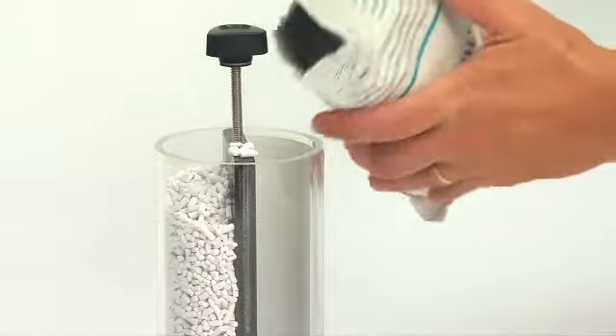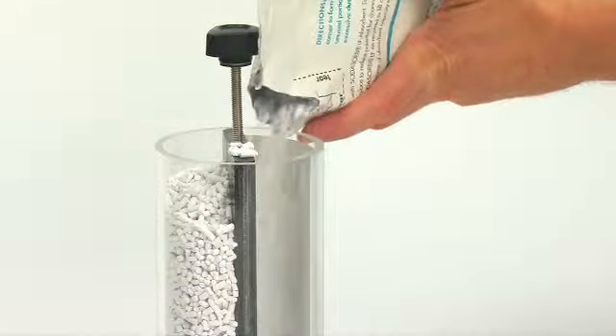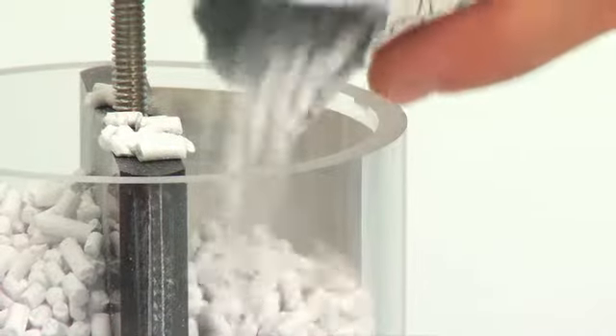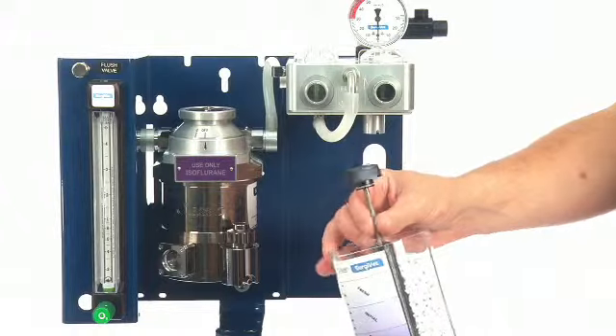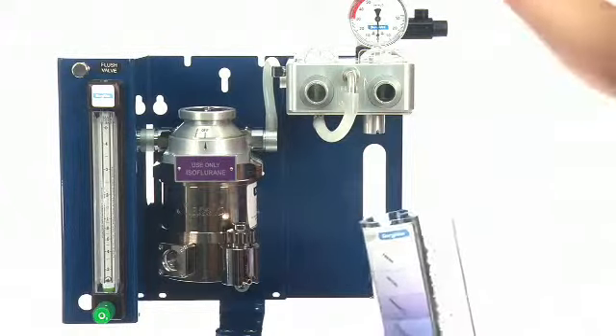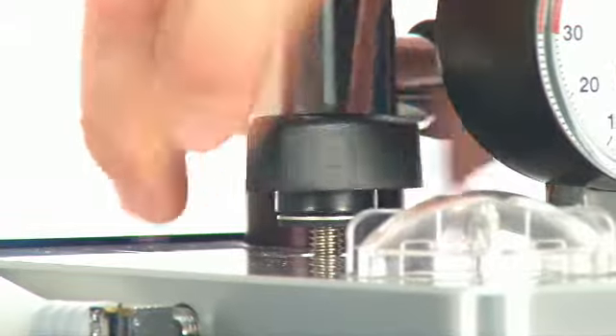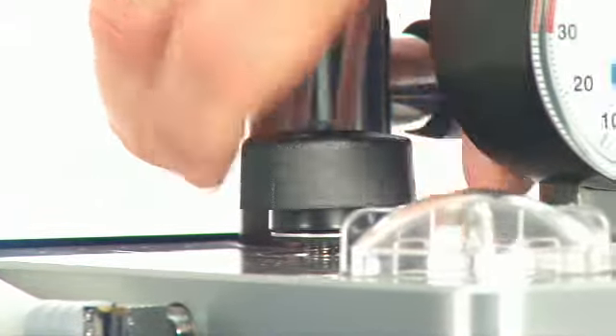Fill the absorber canister with absorbent up to 1/2 to 1 inch from the top of the canister. Once filled, remove the draw knob and align the canister underneath the head of the machine. For proper alignment, the canister has a guide pin that must be seated in the provided guide pin slot under the machine head. When tightening the canister in place, finger tighten only to avoid damaging the canister.